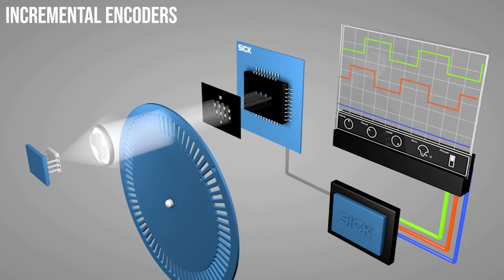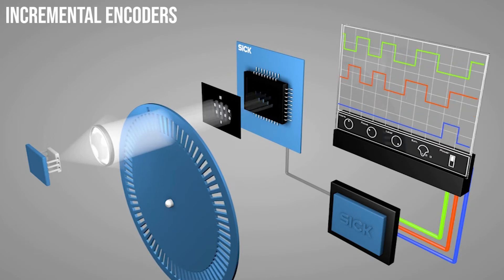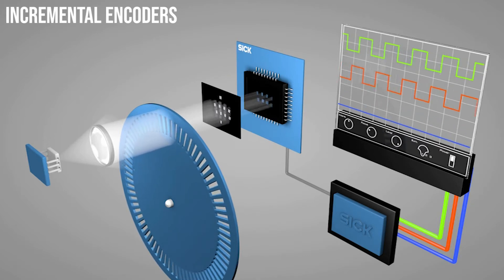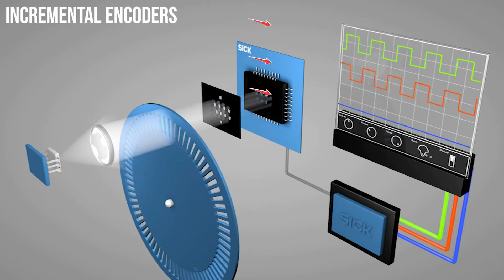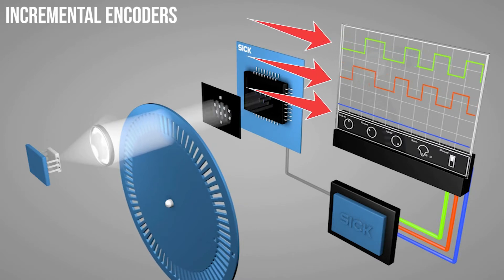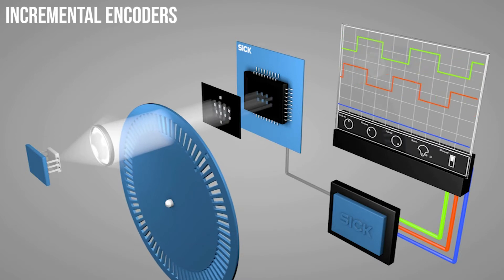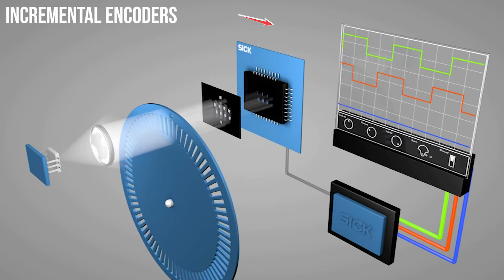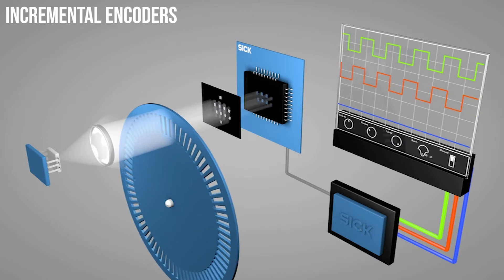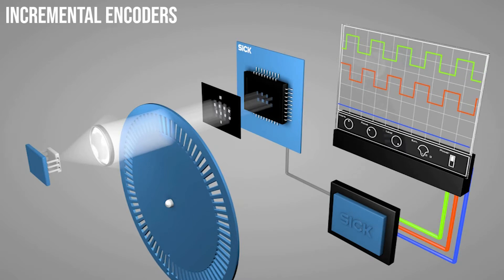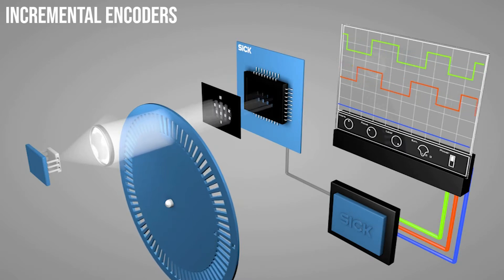How fine a movement is indicated by the pulses per revolution, or how many times the encoder can split one revolution of the shaft turning. You may have noticed as the encoder turns that we're seeing three different signals. These signals are called channels, and are used to determine the direction of the movement as well as for counting revolutions. The two square wave channels are the A and B channel. These channels are offset to each other, and this is required so we can tell when the encoder is moving in one direction or another. This is important when trying to use the encoder for positioning.